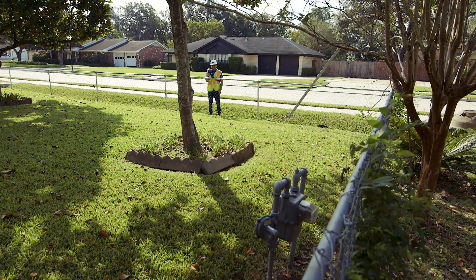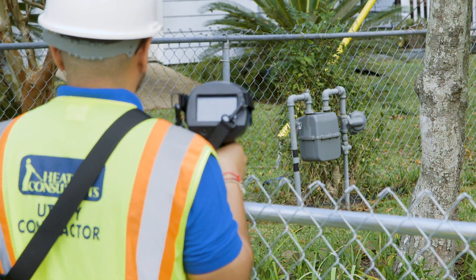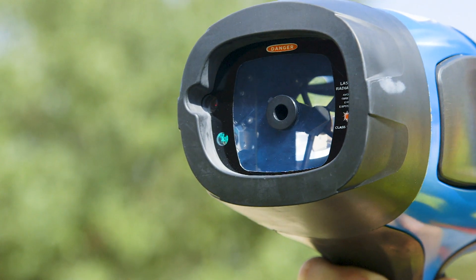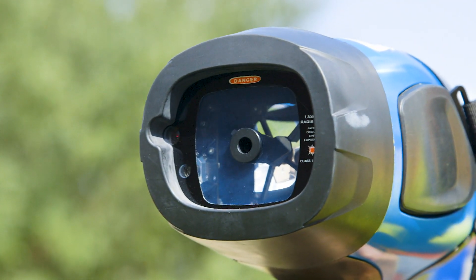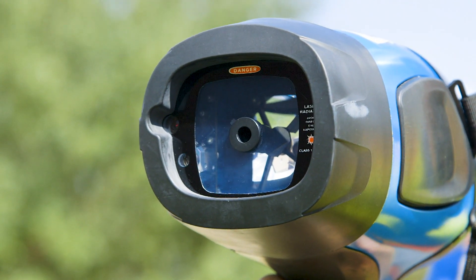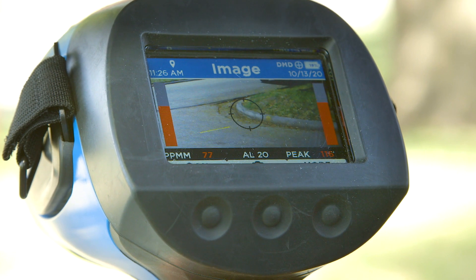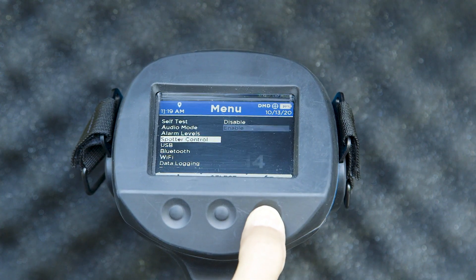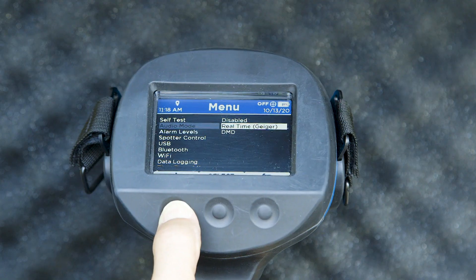While using the Digital Methane Detector, or DMD, no sound will be heard until a detection of methane occurs, ensuring that the RMLD-CS will not alarm due to background methane. Once methane is detected, the DMD mode indicates that gas is present above the alarm level. The alarm will sound, but does not vary with the concentration reading above the alarm level. The user will also see a visual indication of the DMD detection on screen in the form of readings, bar graphs and image reticule turning red. To enter DMD mode, press the menu button, select audio mode, then select DMD.